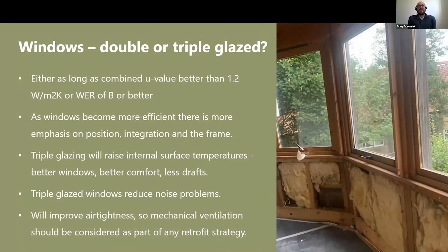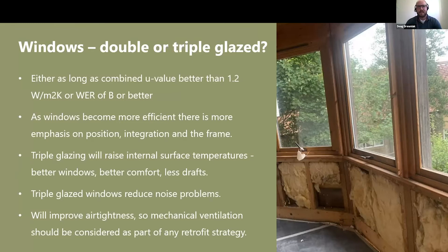The next item to look at is windows, especially double or triple glazed units. Nowadays there's not that much difference between a very efficient double glazed unit and an inefficient triple glazed unit. What you typically want to aim for is a combined U-value of glazing and frame of better than 1.2. Another useful metric to be aware of is the window energy rating — you're typically looking at B or better in terms of that rating.